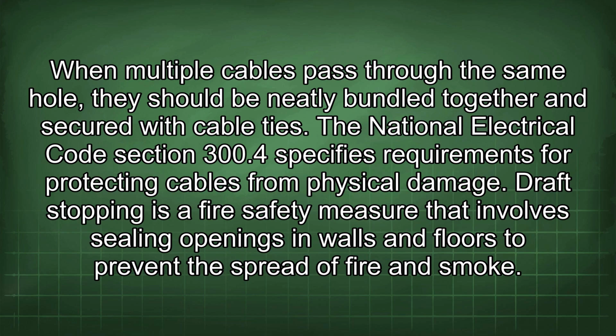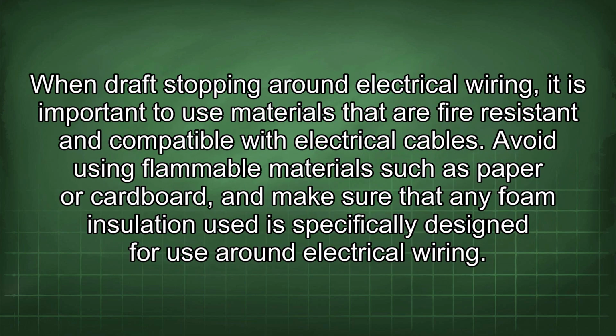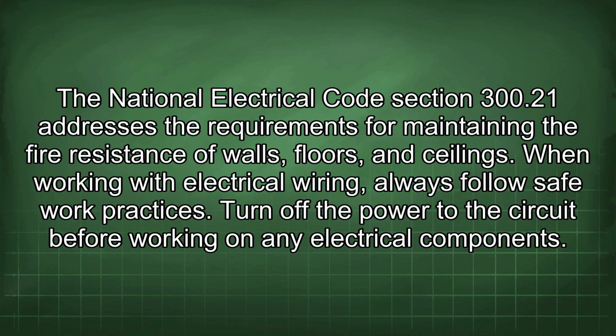Draft stopping is a fire safety measure that involves sealing openings in walls and floors to prevent the spread of fire and smoke. When draft stopping around electrical wiring, it is important to use materials that are fire resistant and compatible with electrical cables. Avoid using flammable materials such as paper or cardboard, and make sure that any foam insulation used is specifically designed for use around electrical wiring. The National Electrical Code Section 300.21 addresses the requirements for maintaining the fire resistance of walls, floors, and ceilings.